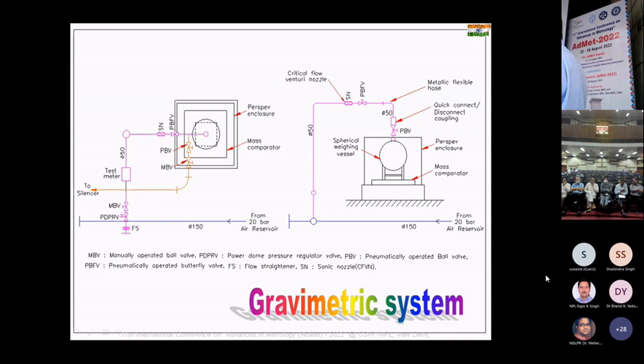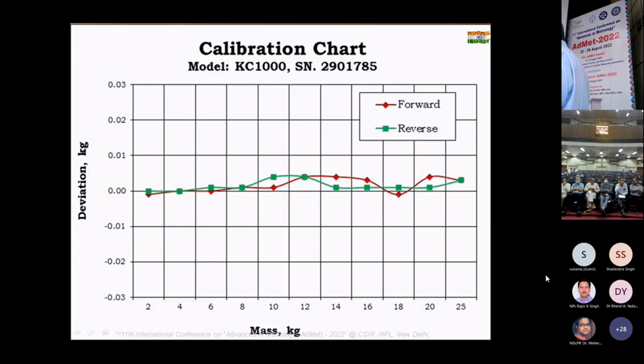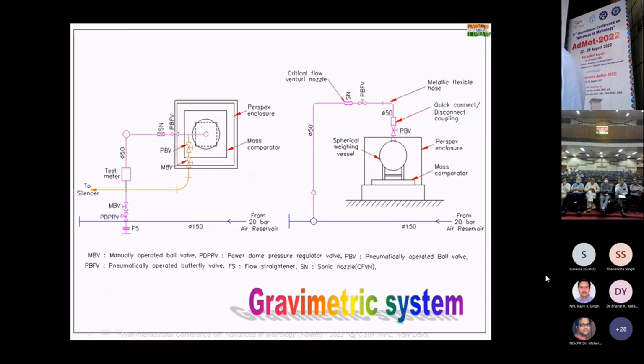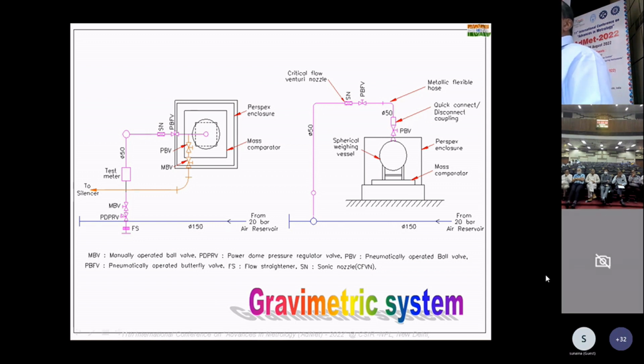So we have to account for the loss of air, which is not directly coming into the comparator. This we call the control volume. That volume is also determined by a gravimetric system. We fill it with water, and from the weight and density, we determine the volume. From the initial and final pressure and the initial and final temperature, we know the density difference. From the volume, we can estimate the mass of air discharged for decoupling. That mass will be added to the final mass, and then we take the total mass.